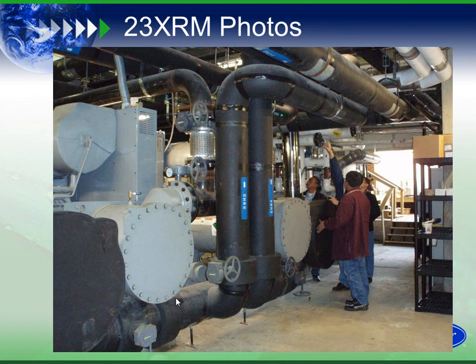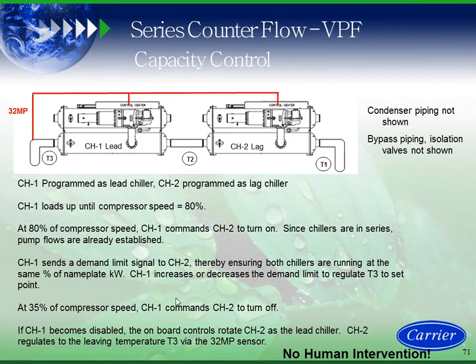Here's a photo of a 23XRM where I basically have a marine water box on the sides, and they're connected to one another. So there's a photo of a chiller plant operating in series counterflow. From a control standpoint, how do we want to control it? Again, I have chiller 1 programmed as the lead chiller. Chiller 2 is programmed as the lag chiller.